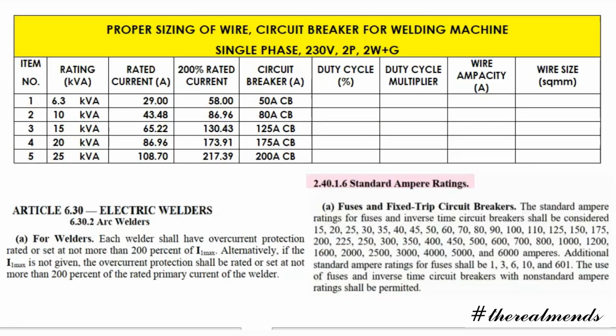2.40.1.6, standard ampere ratings. So for our 6.3 kVA, we have a rated current of 200% times 58. So the next circuit breaker, if you look at the table in our PEC code, we have 50, 60, 70, or 80. It says in Article 6.30 that the overcurrent protection should be not more than 200% of the Imax, so it cannot exceed that. Therefore we can use a 50 ampere CB.